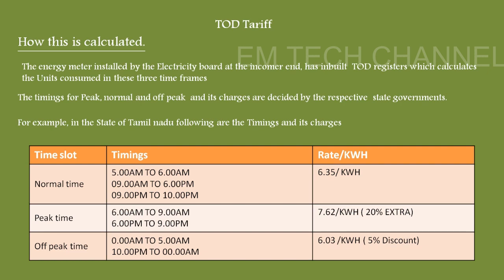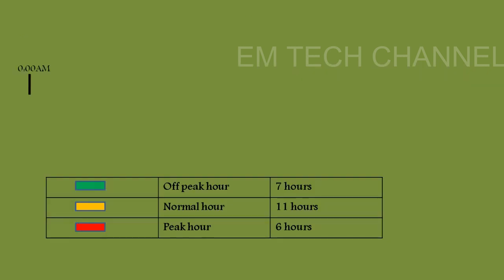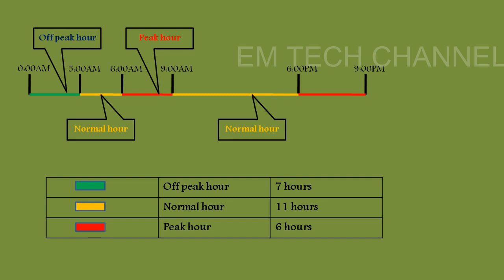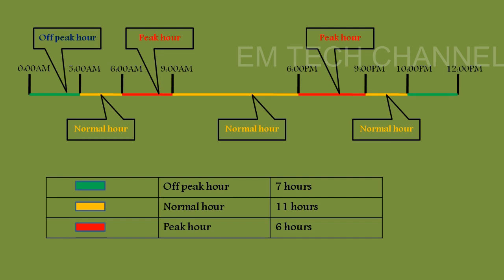Off-peak time is from midnight 12 AM to morning 5 AM and from 10 PM to midnight 12 AM. In this time, energy charges are 6.03 rupees per kilowatt hour, as the government offers a 5 percent discount on normal consumption charges. Looking at the full timeline: 12 AM to 5 AM is off-peak, 5 to 6 AM is normal, 6 to 9 AM is peak, 9 AM to 6 PM is normal, 6 to 9 PM is peak, 9 to 10 PM is normal, and 10 PM to midnight is off-peak — divided into seven time frames.